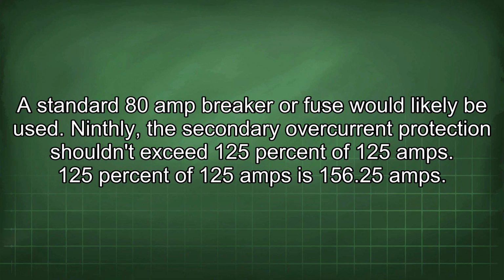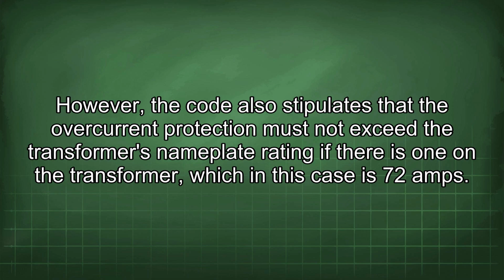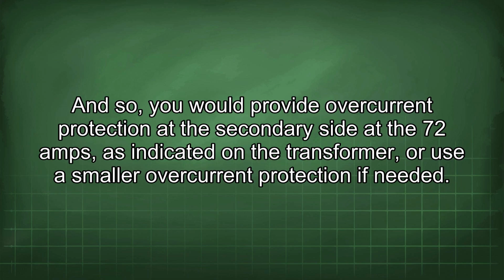Ninthly, the secondary overcurrent protection shouldn't exceed 125% of 125 amps. 125% of 125 amps is 156.25 amps. However, the code also stipulates that the overcurrent protection must not exceed the transformer's nameplate rating if there is one on the transformer, which in this case is 72 amps. And so, you would provide overcurrent protection at the secondary side at the 72 amps, as indicated in the transformer, or use a smaller overcurrent protection if needed.